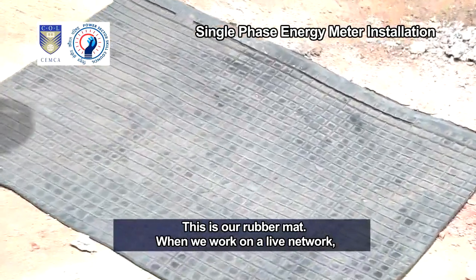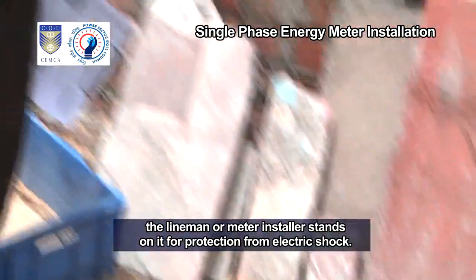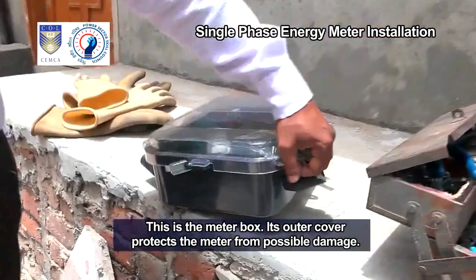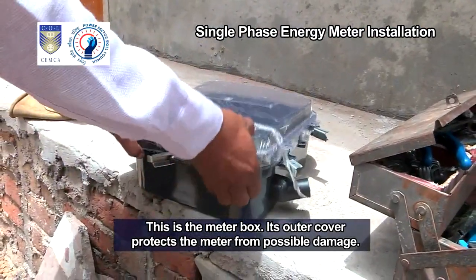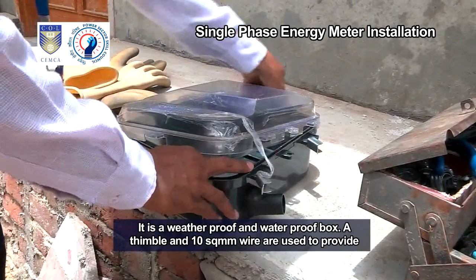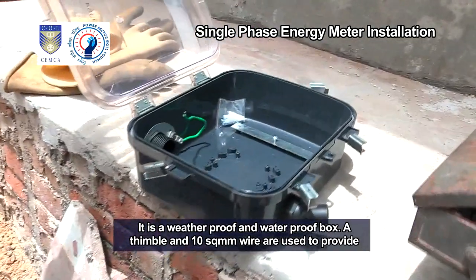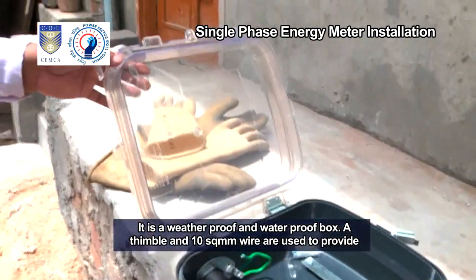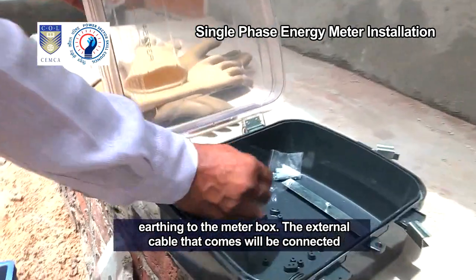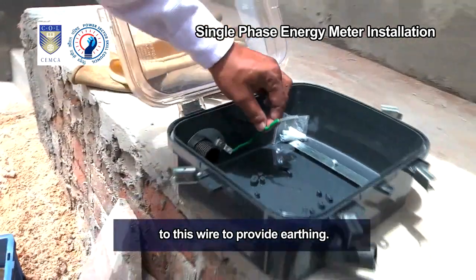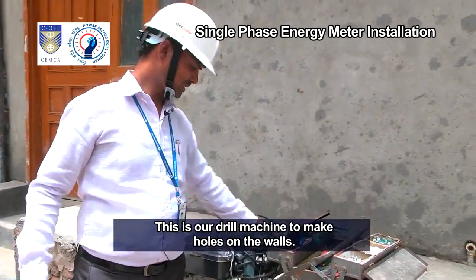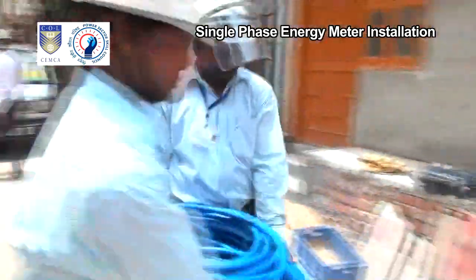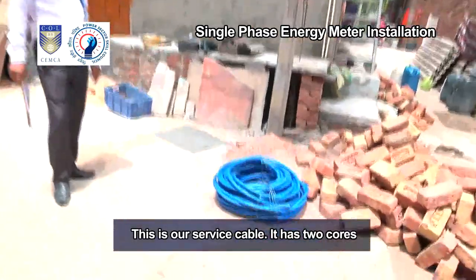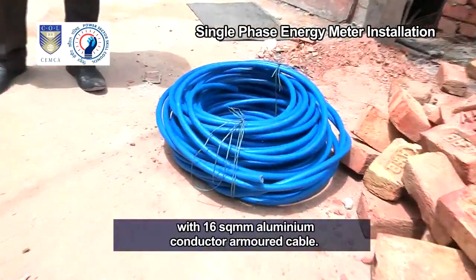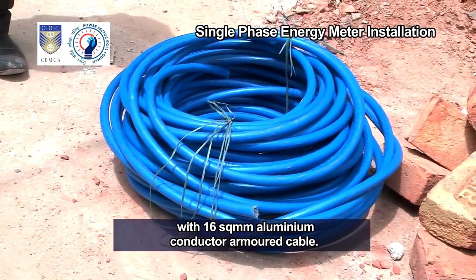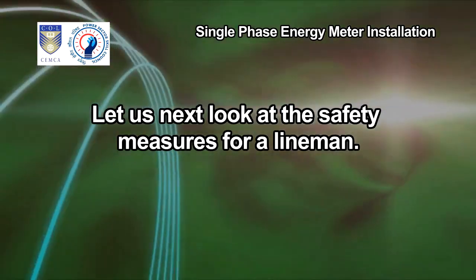When we work on a live network, the lineman or meter installer stands on it for protection from electric shock. This is the meter box. Its outer cover protects the meter from possible damage. It is a weatherproof and waterproof box. A thimble and 10 square mm wire are used to provide earthing to the meter box. The external cable that comes will be connected to this wire to provide earthing. This is our drill machine to make holes on the walls. This is our service cable. It has 2 cores with a 16 square mm aluminium conductor armored cable. Let us next look at the safety measures for a lineman.